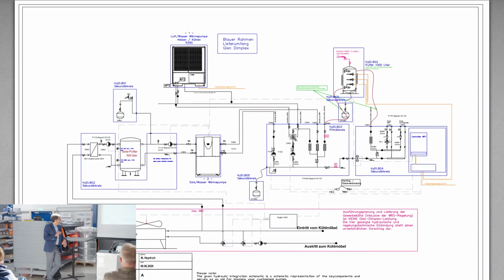However, this machine is also available to produce cooling during the summer. It is a reversible machine based on propane R290 refrigerant, and it is reversible with a special four-way valve, which also reverses the water loop on the condenser. So during the summer we can also produce a cooling medium with low temperature for supply. During the winter, we are extracting the energy for heating from the cabinets.